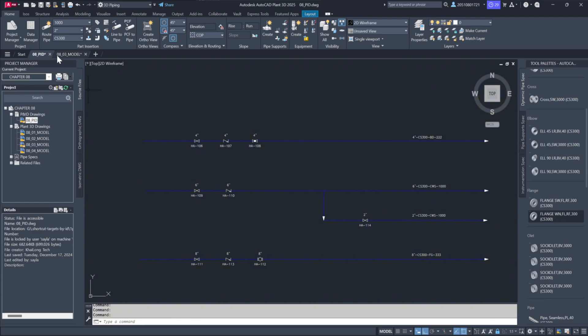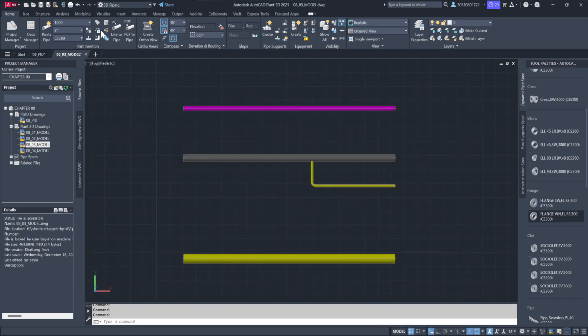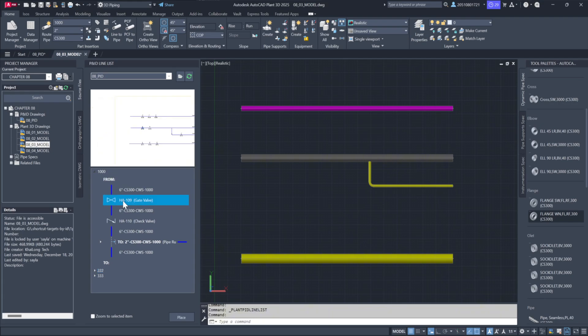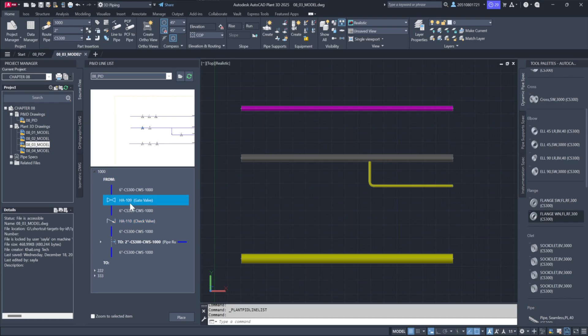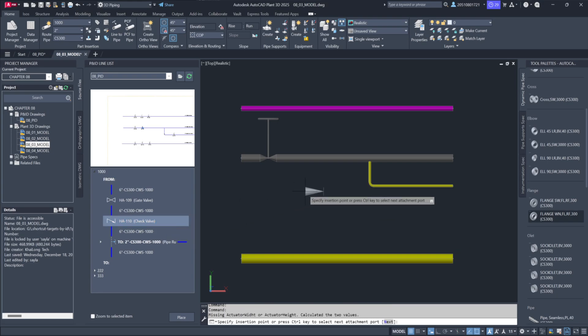Let's move on to placing valves on line 1000. For this line, a 2-inch gate valve is needed on the smaller section, followed by a 6-inch gate valve and check valve on the larger section. Locate line 1000, highlight the gate valve, right-click, and select Place Item. Drag and drop it into position within the model. Repeat the process for the check valve and any additional components as required.